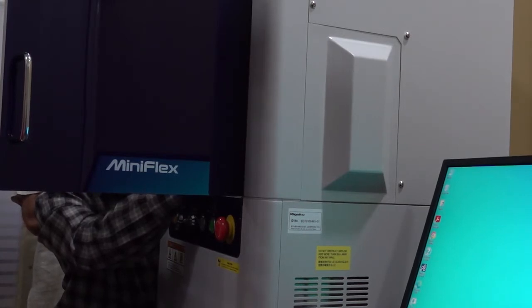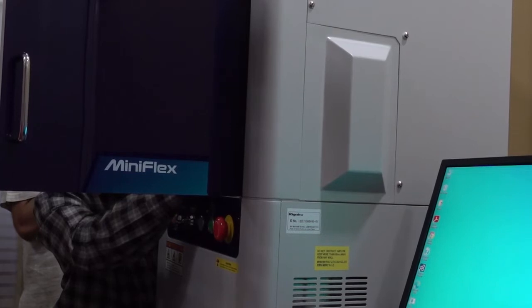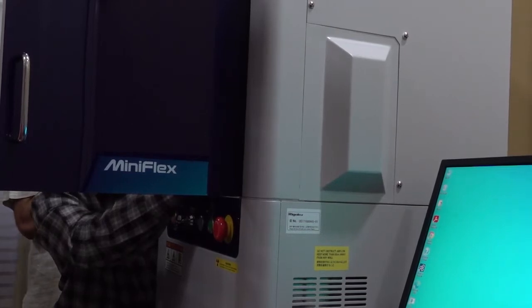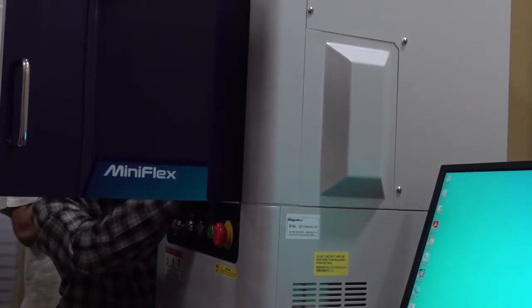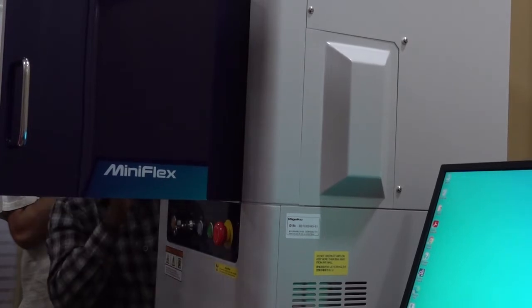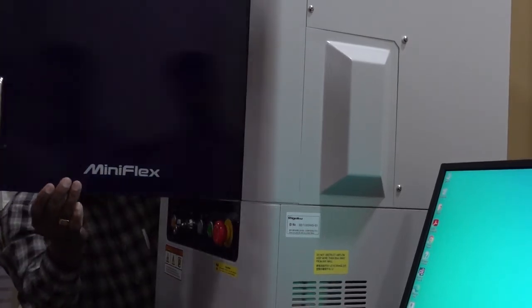Earlier they were using some 0D detector. That is 10 or 15 degrees per minute maximum speed. This one is 100 degrees per minute, and the intensity is also more in this detector. So now I will start this machine.